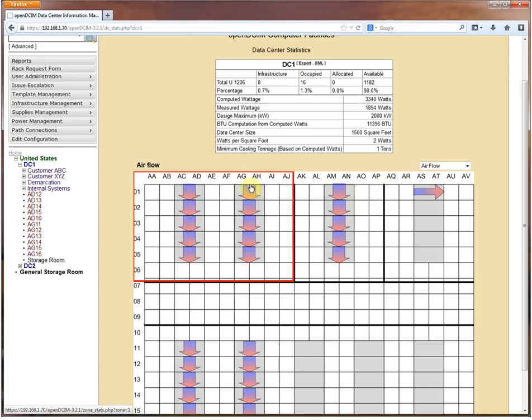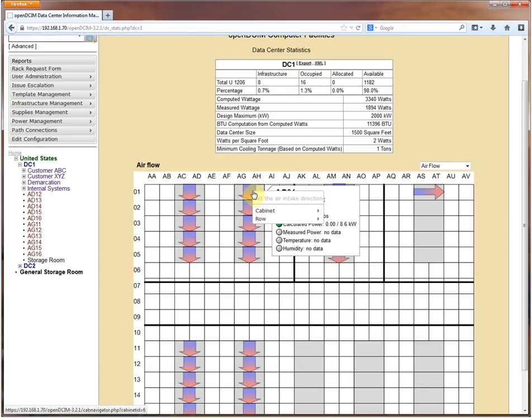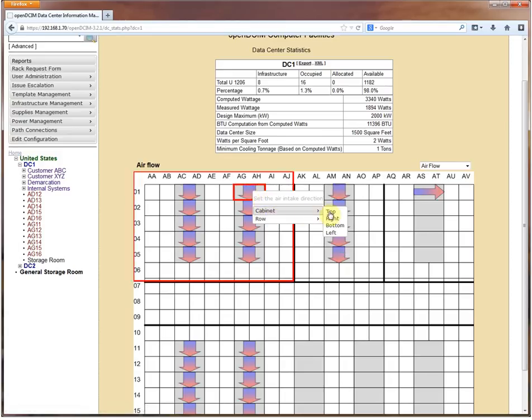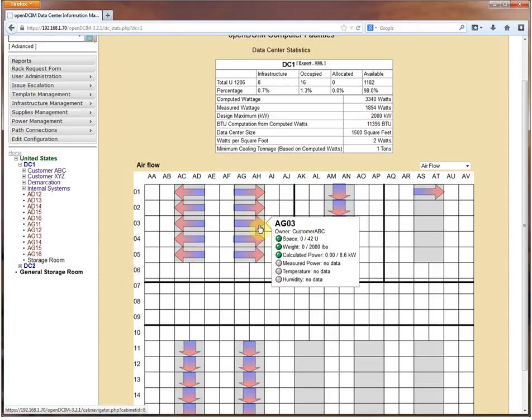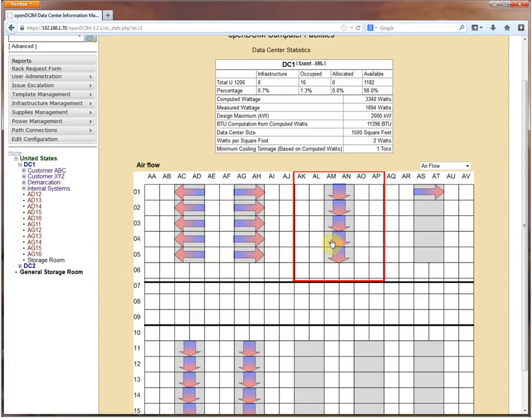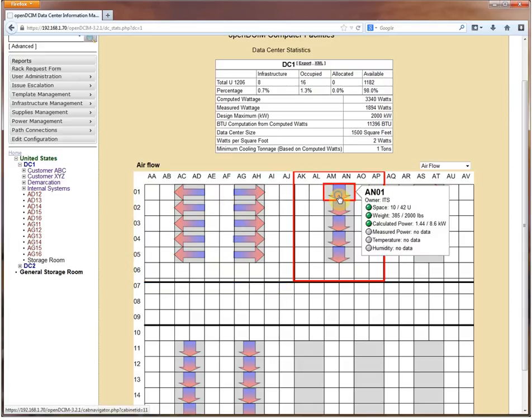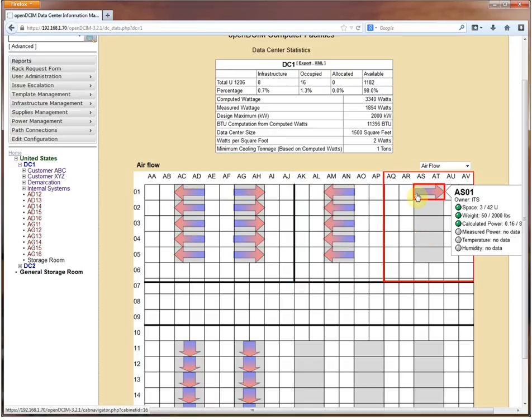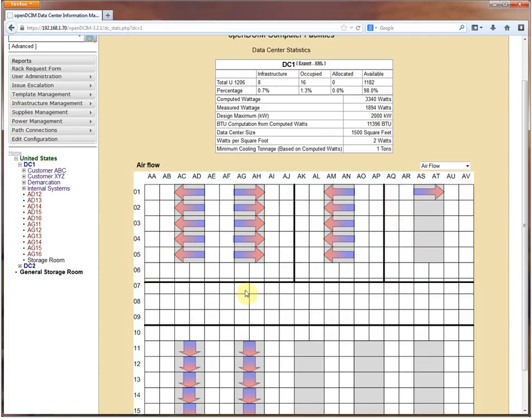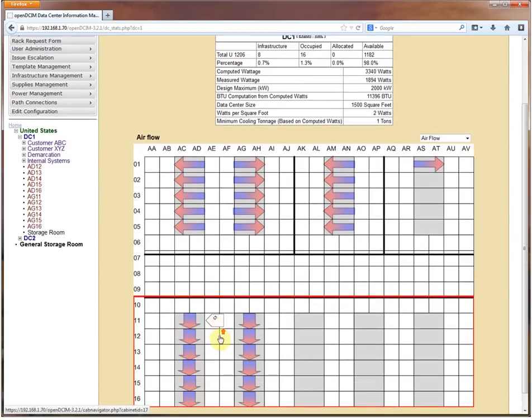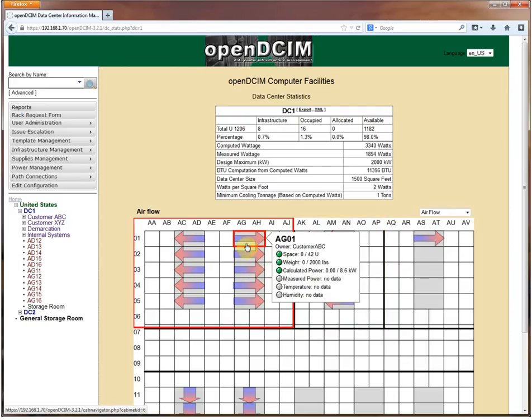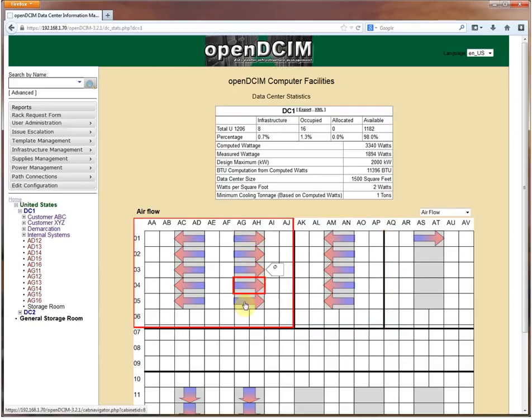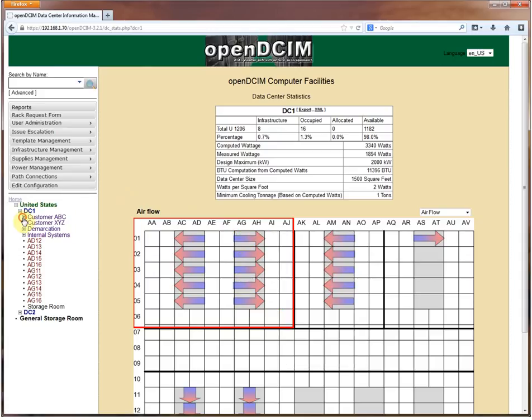That's the one-off way to do it. The easier way, if you've already got your cabinets set into rows, when you click on a cabinet in that row with the right mouse button, you can either set the cabinet's intake direction or you can set it for the entire row. So here it's left and here it's right. Now we indicate that this is our cold aisle and then this would be our exhaust side. So this would be to the right and this would be to the left. So here we've got cold, cold, cold.